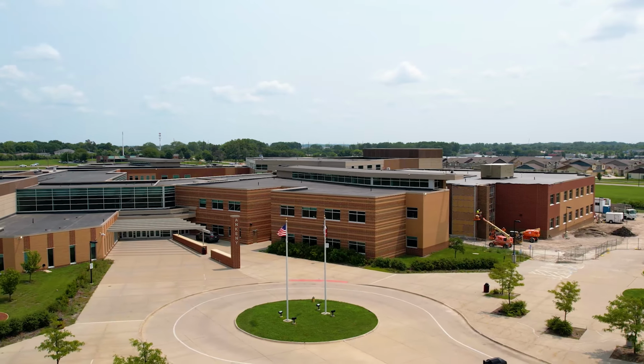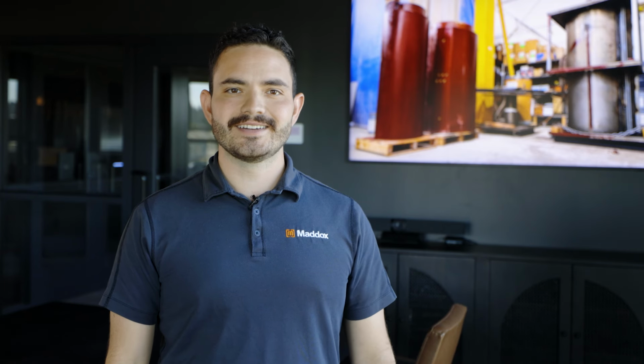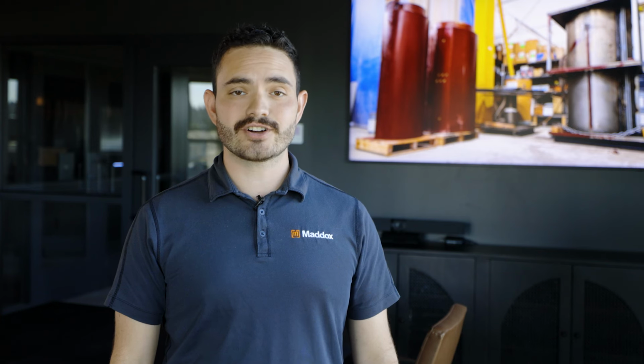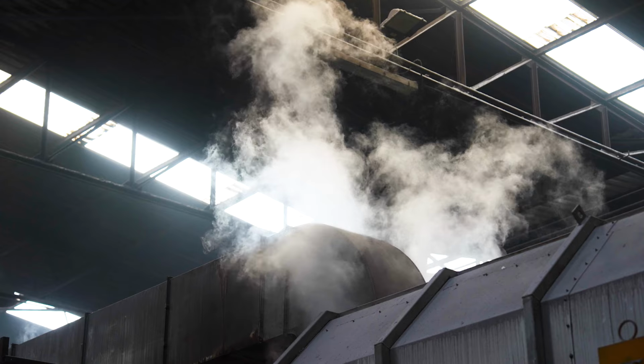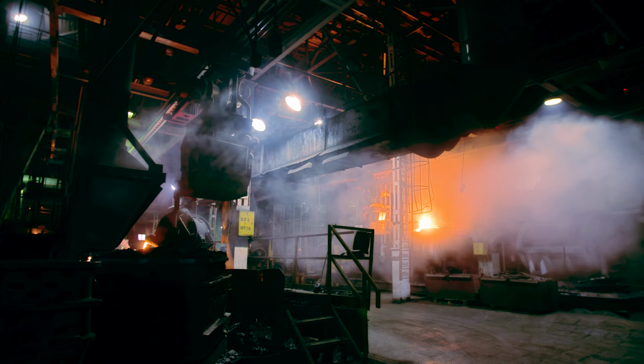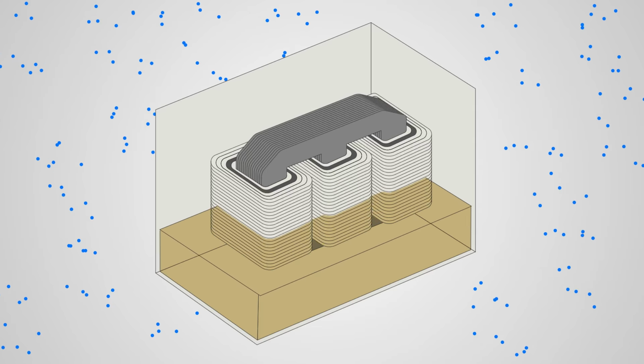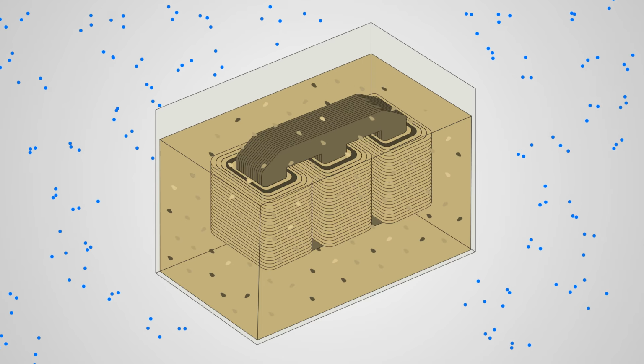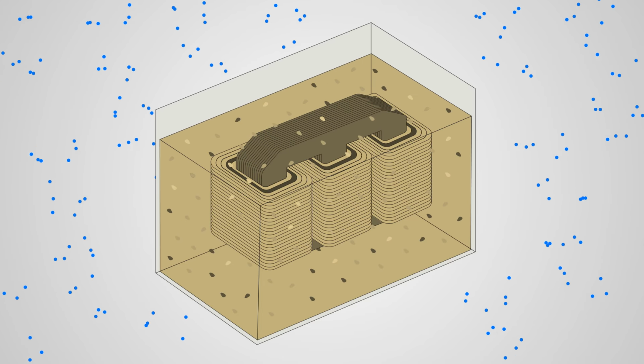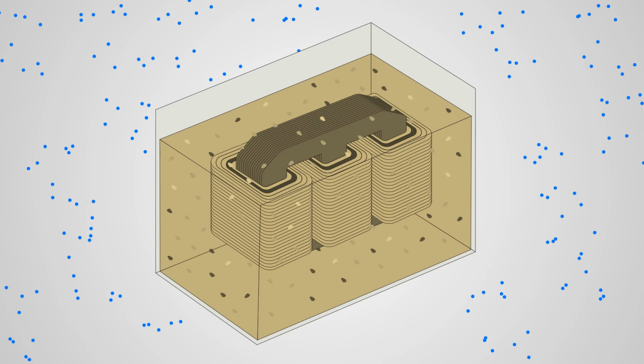This is ideal in areas like commercial buildings or schools. If you want to learn more about transformer noise, take a look at our other video on why transformers hum. Third, no moisture. Typical dry type transformer windings are exposed to ambient conditions like humidity or moisture. A cast resin transformer blocks any moisture from getting into the windings, even if your environment is extra humid. No moisture can get past the resin.